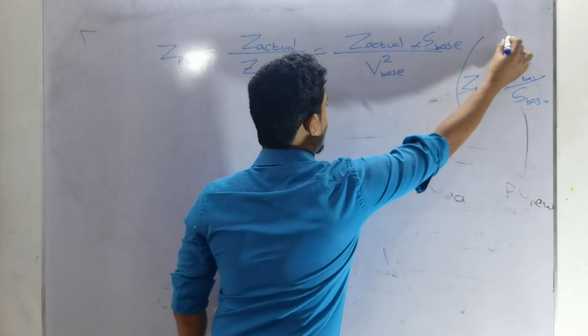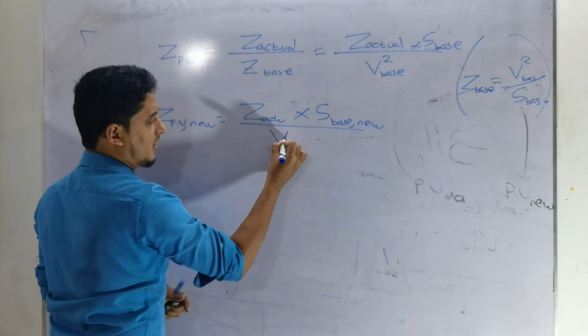Now we will define the new per unit: new per unit equals the actual impedance multiplied by the new base power divided by the new base voltage squared. The old per unit equals the actual value, which doesn't change, multiplied by the old base power divided by the old base voltage squared. So this is the old per unit and this is the new per unit. Now we will divide these two equations.